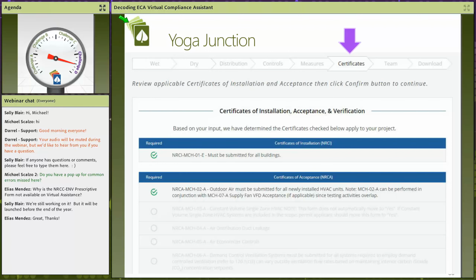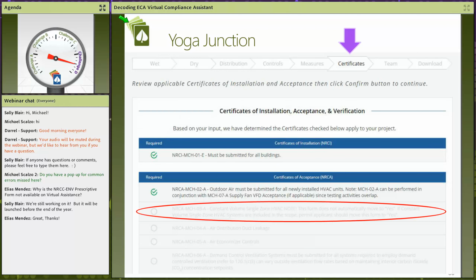When should the testing happen? What happens if someone changed things out in the field after it's been tested? This is when I can go in and look at that summary -- this is where the summary is important -- and go to these certificates. This tool, just like the forms, auto-populates what installation forms are required, provided by the contractor, and what acceptance testing is required for these specific features.